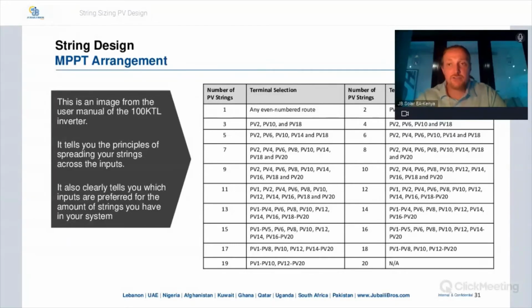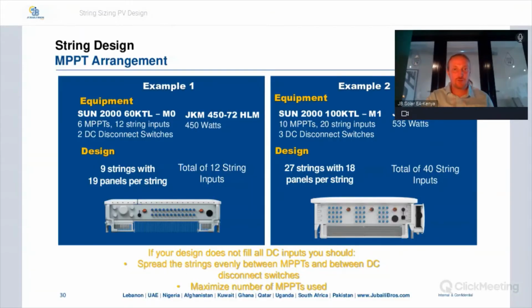And I can tell you the theory behind this. Number one is that these Huawei inverters have DC disconnect switches. Let me show you here. We're looking at the two inverters. On both of them you can see the red circles. Those are DC disconnect switches. You can switch the power to the DC on and off. Each switch controls a block of MPPTs that it's next to.